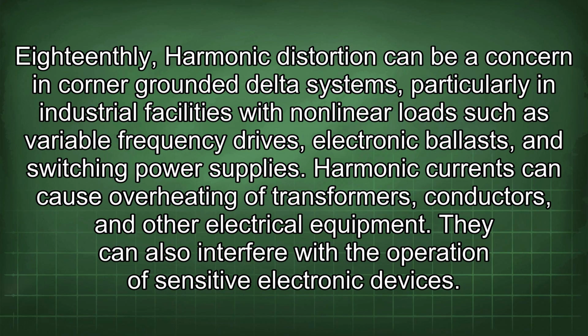18thly, harmonic distortion can be a concern in corner-grounded delta systems, particularly in industrial facilities with nonlinear loads such as variable frequency drives, electronic ballasts, and switching power supplies.